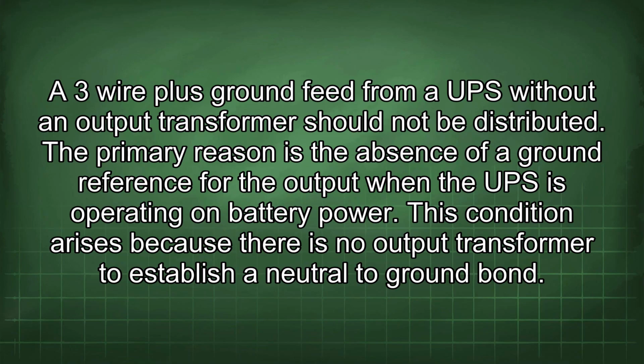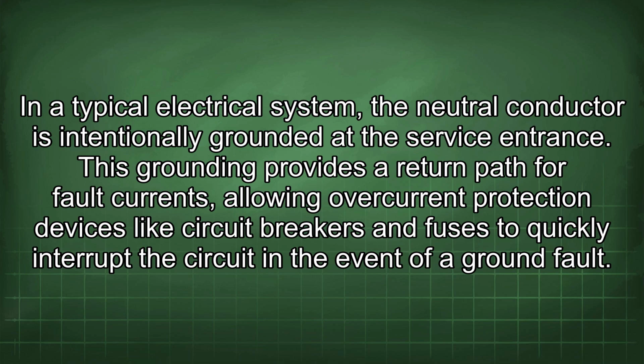A 3-wire plus ground feed from a UPS without an output transformer should not be distributed. The primary reason is the absence of a ground reference for the output when the UPS is operating on battery power. This condition arises because there is no output transformer to establish a neutral to ground bond. In a typical electrical system, the neutral conductor is intentionally grounded at the service entrance. This grounding provides a return path for fault currents, allowing overcurrent protection devices like circuit breakers and fuses to quickly interrupt the circuit in the event of a ground fault.